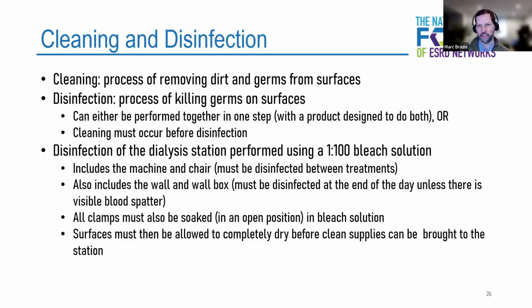And so there's sort of two ways that you can approach cleaning and disinfection. Sometimes these can be performed together as one step. There are some products that will simultaneously clean dirt and grime off and disinfect at the same time. Or it can be done as two steps. And if it's done as two steps, it's important that cleaning always occurs before disinfection. Because again, that disinfecting solution is not going to have a chance to really fully get to the surface to kill all of the germs that are there if there's still dirt or grime on top of it.